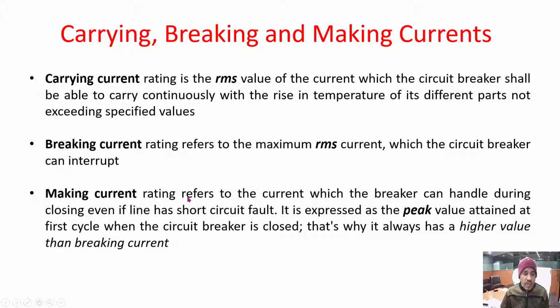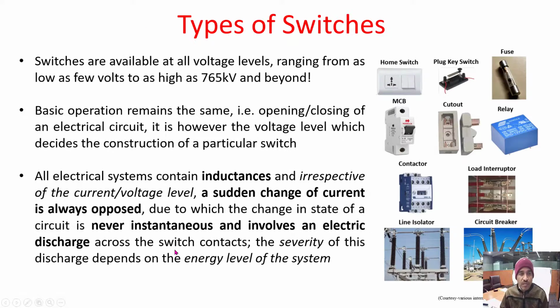And the making current rating refers to the current which the breaker can handle during closing, even if the line has a short circuit fault. Even in that condition, it should be able to make, meaning connect. So it is expressed as the peak value attained in the first cycle when the circuit breaker is closed. That is why it is always higher than the breaking current, because it is the peak value attained in the first cycle while making, during the transient itself. So this is always greater than the breaking current.